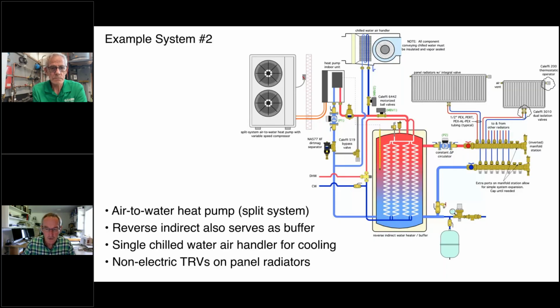We have copper coils inside. That's for heating domestic hot water. And we're also using the shell as a buffering volume for space heating. Space heating's panel rads with TRVs, variable speed circulator. We also have cooling going on with a single chill water air handler.